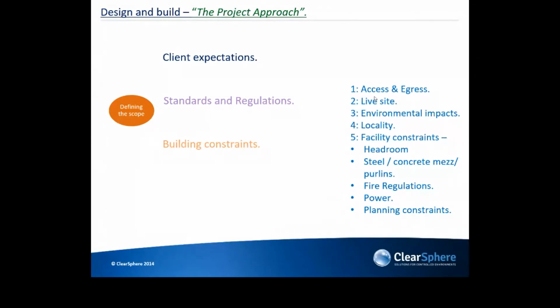This pharmacy was built in without major constraints, because a lot of times these pharmacies tend to be put in a basement or you're working between a floor and a slab space, which is quite constrained. So headroom was very beneficial here, and it meant we were able to install attenuators on every leg of ductwork, which allowed the facility to be super quiet in the end. We had readings of 32, 33 decibels, which was very, very good.